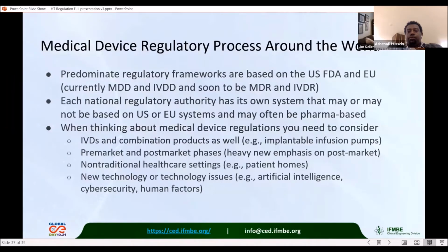When thinking about medical device regulations, there are several things that you need to consider. First off, it's not just about infusion pumps and patient monitors, but covers in vitro diagnostics, which are considered medical devices, and also combination products, for example, implantable infusion pumps. There are pre-market and post-market phases, and particularly going forward under the soon-to-be enacted medical device regulations, there is heavy new emphasis on the post-market process. There is more and more consideration around non-traditional healthcare settings, like in patient homes, and more considerations in the regulatory process around new technology issues. So for example, artificial intelligence, cybersecurity, and human factors.